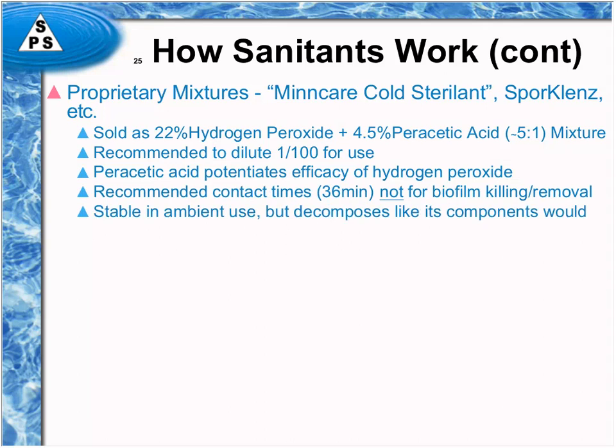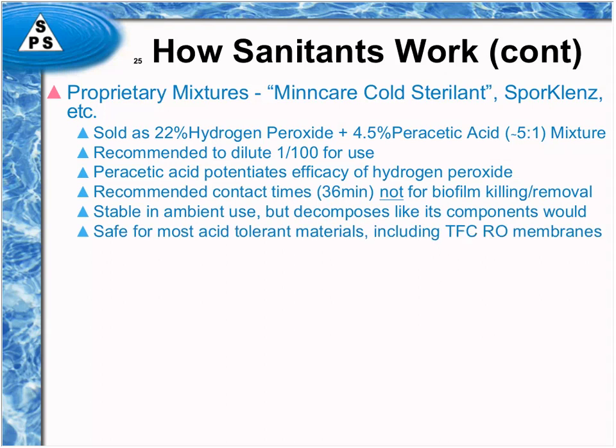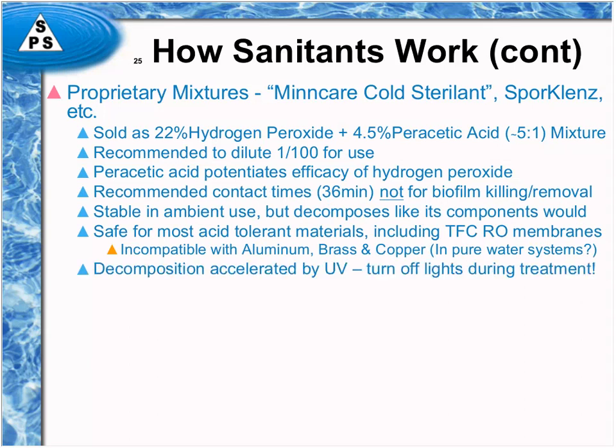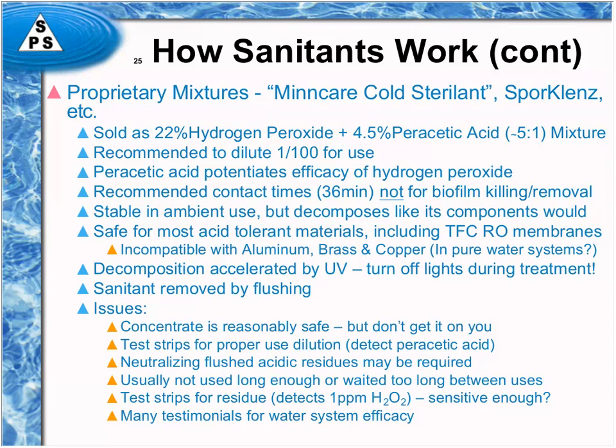It's stable in ambient use and does decompose just as its components would decompose. Safe for most acid-tolerant materials, including RO membranes, but it's incompatible, obviously, with some other metals, but you don't find those in water systems anyway. So decomposition is aided by UV, so turn those lights off, and you remove it by flushing. And it's got some of the same issues.